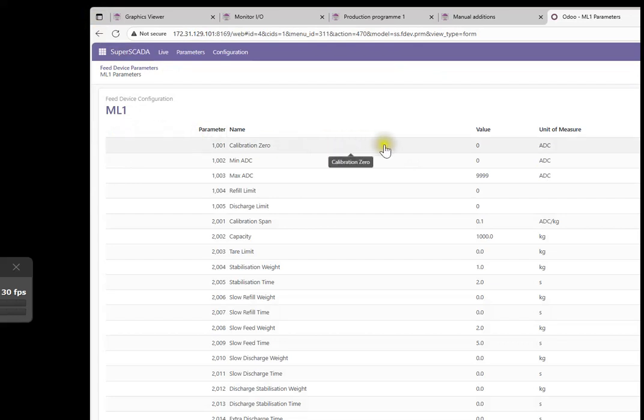The value that comes in from the PLC will be 0 before it starts, and the calibration span here is 0.1. So for every 10 ADC units coming in from the PLC, it's a reading of 1 kilo. So 1 kilo means it goes up by 10. If you want to, you can change the calibration span here.